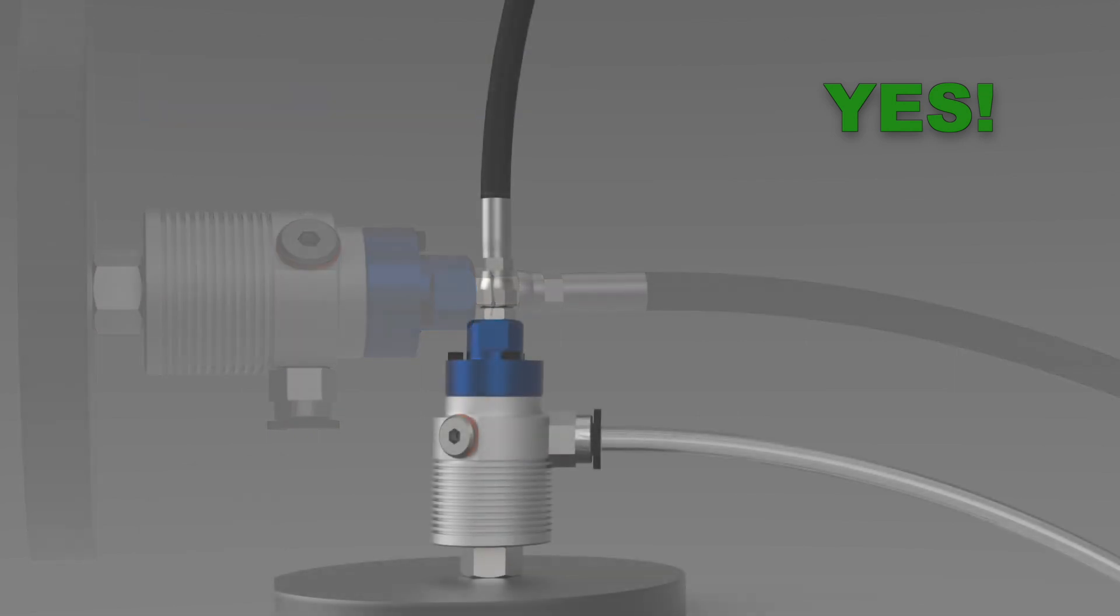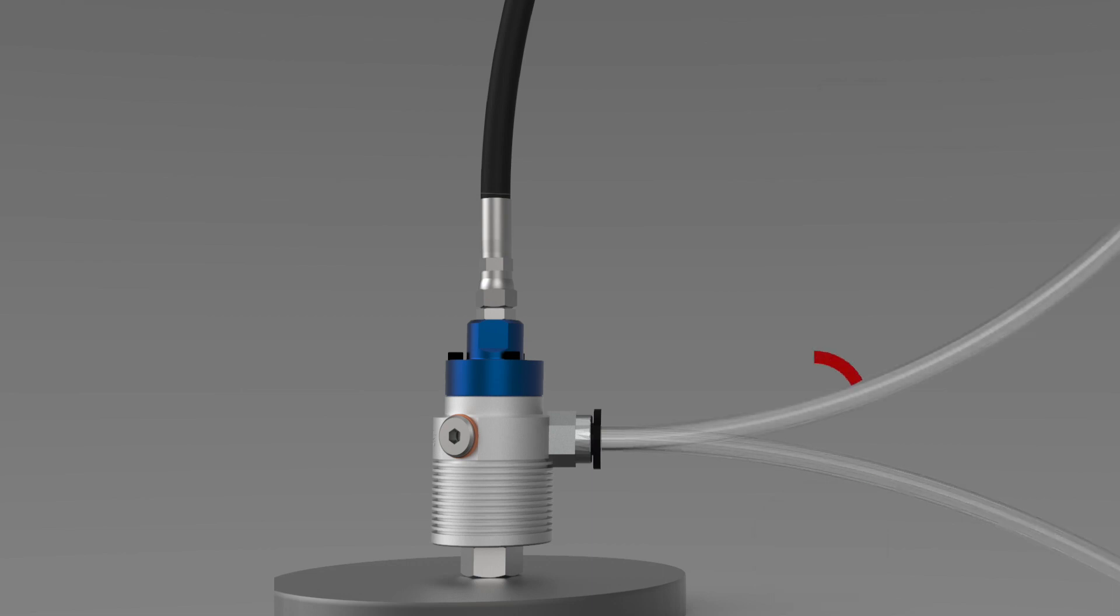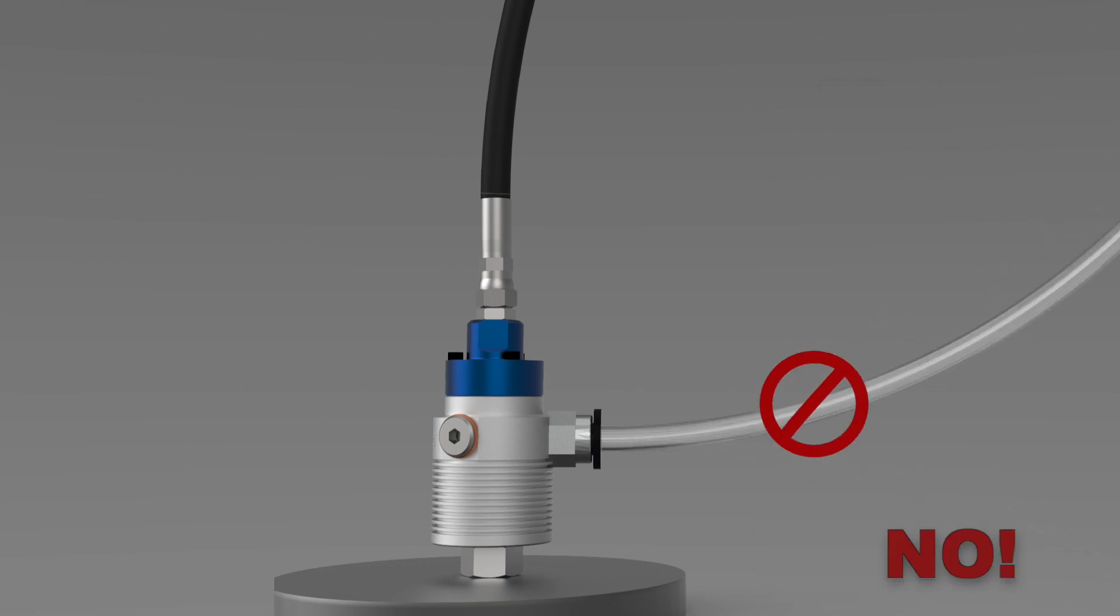In a vertical installation, the six o'clock position is not relevant, but it is still essential that the drain line slopes downward. If it flows upward instead, the union's bearings can be flooded.